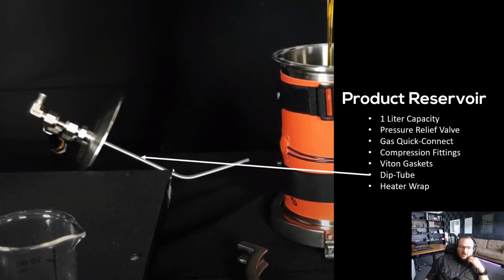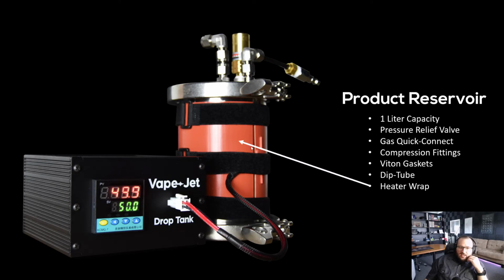This dip tube here allows us to pull the oil from the very bottom of this reservoir when it's inside the system, so that you only have about 1 milliliter of residual oil inside this canister when you go to change it out. And finally, the heater wrap, which is put around each one of our systems, and that is so that you can keep the oil inside this canister at a specific temperature. And you see here it's connected to our drop tank system, which is just a preheater. This allows you to preheat the canister before it goes in the system to allow you to perform quick swaps.